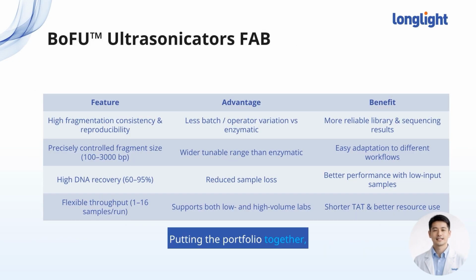Putting the portfolio together, the key value of BoFU is stable physics instead of fragile chemistry. All models generate a uniform cavitation field that can be tuned from about 100 BP up to 3000 BP, giving labs much more control over insert size than typical enzymatic kits. Because fragmentation is a physical process, the results are independent of reagent chemistry or chemical conditions, incubation timing, or who happens to be on shift that day.